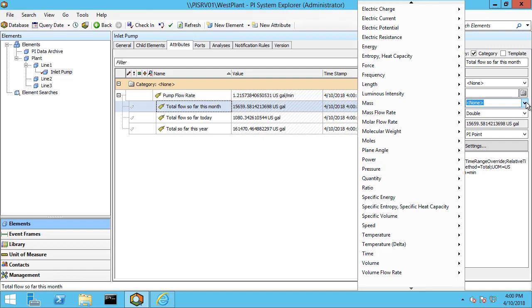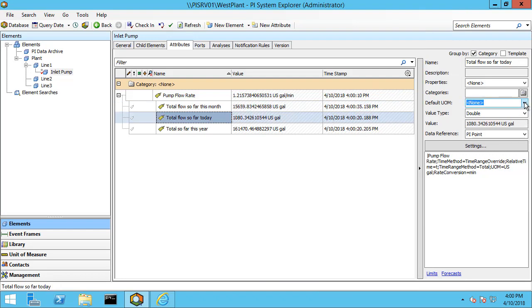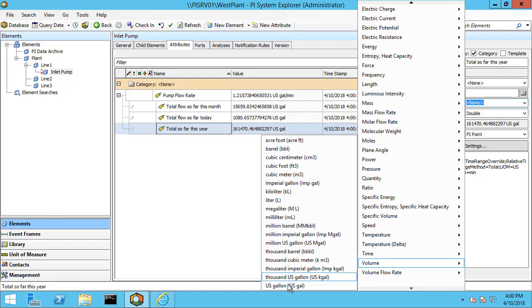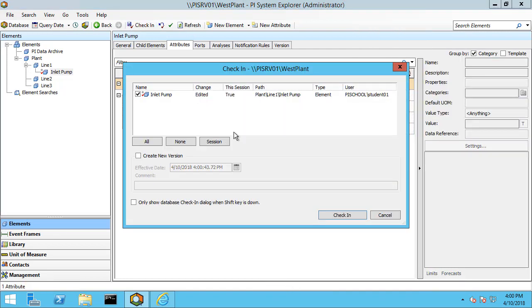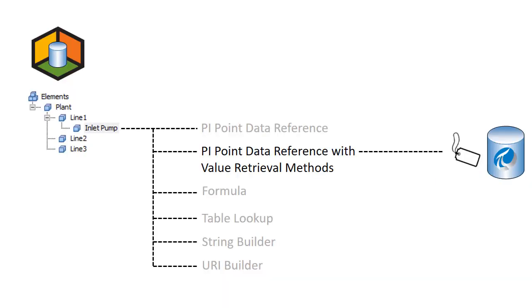Let's make sure that we set our units of measure explicitly on what we would like to output. These will not be saved to PI tags. So here we have the total flow so far today, this month, and this year as PI Point data references with value retrieval methods. Now that you understand how the time context of the client interacts with value retrieval methods of PI Point data references, you can set up summary or single value calculations and understand how different clients interact with these settings.